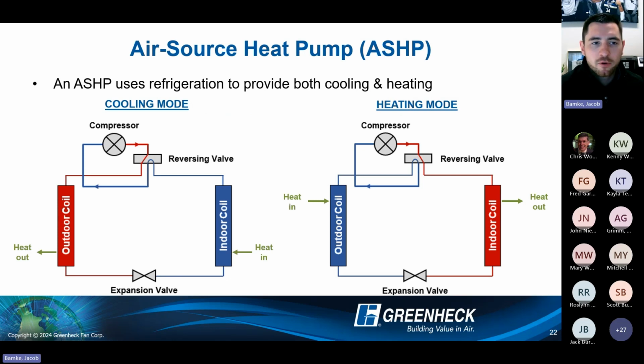So general overview real quick, I'm sure you guys are well aware of how it works, but essentially using that same DX system that you'd use for cooling to now reverse the flow of refrigerant and use it for heating. So essentially we're changing our evaporator and condenser coil and just flipping the purpose of those so that in heating mode, we can reject the hot gas from that compressor to that indoor coil and heat up that cold air that's coming in. And then just grab the heat. Even though it's cold outside, we can still grab heat out of that outdoor air.